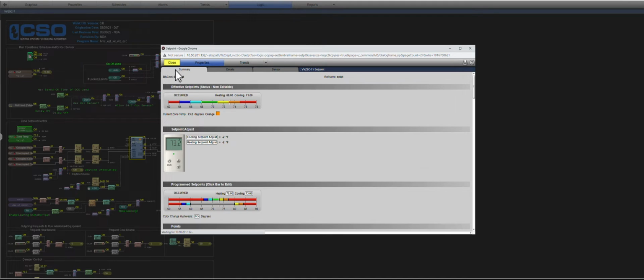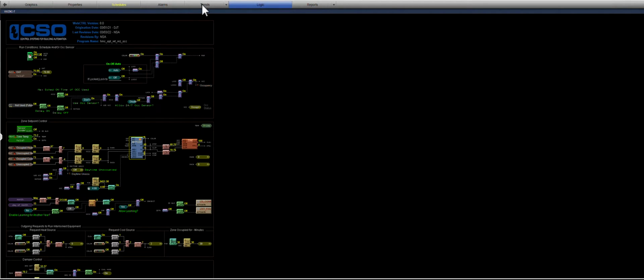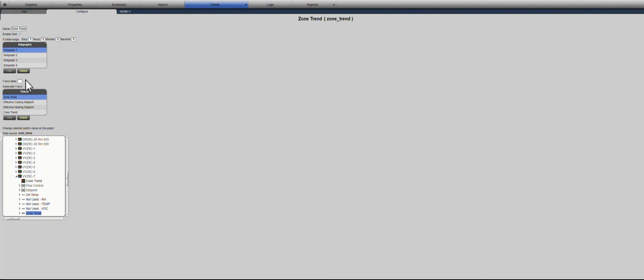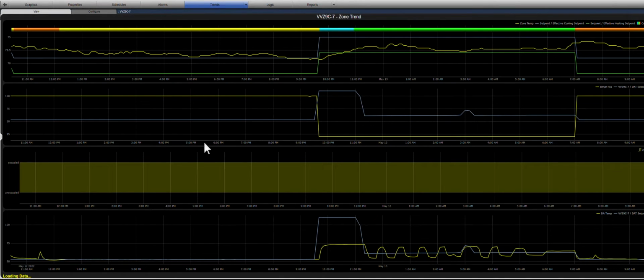So what they've done is they've gone to the thermostat and probably turned it to the bottom. Let's see if we go to trends. We'll go to the view here. Not sure why we ended up in the configure tab, but all right. Let's look at our zone trends for a moment and see what led to the zone being not in green, but being off. This is taking a little while to load up. They are doing downloads on other floors, so the network is a little busy today.